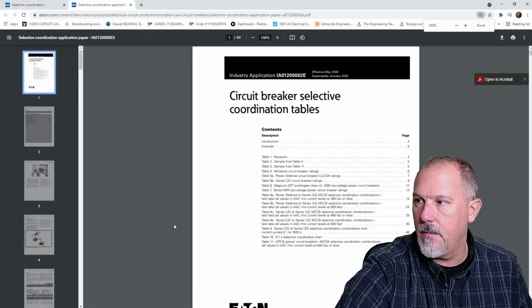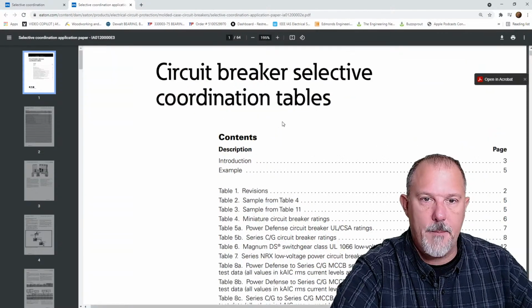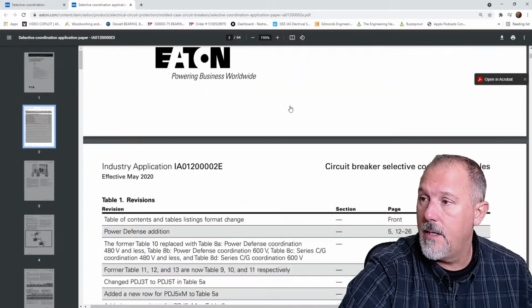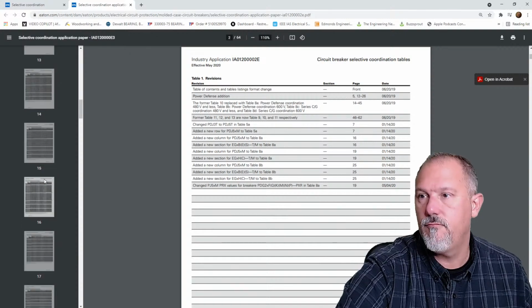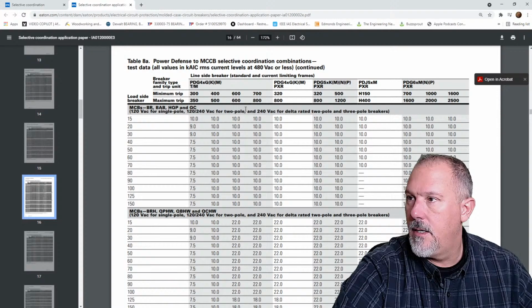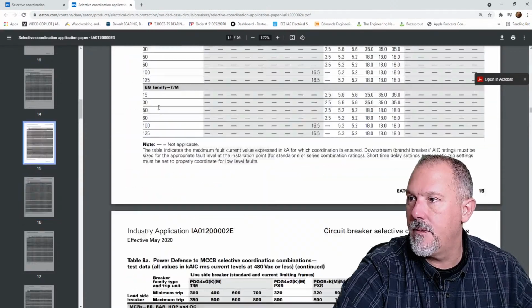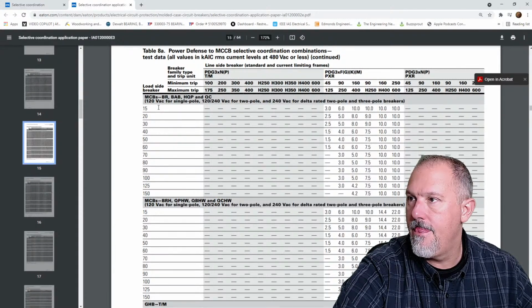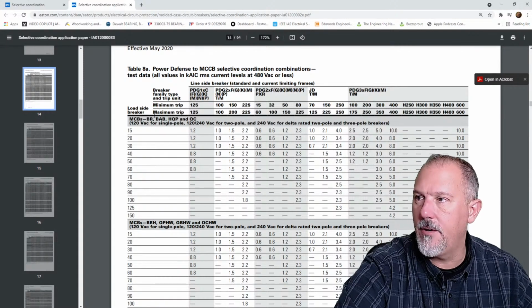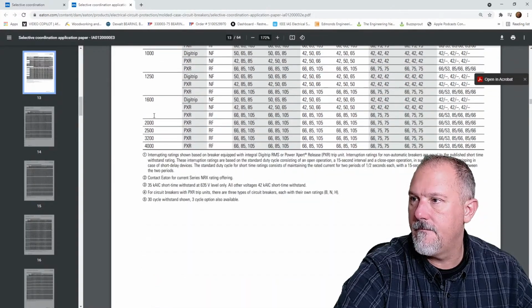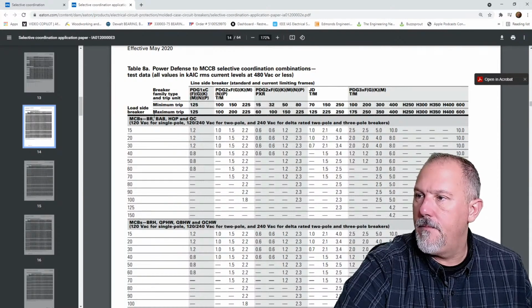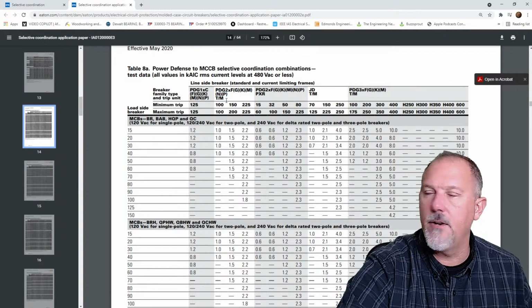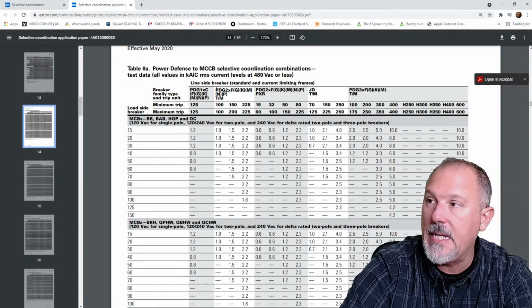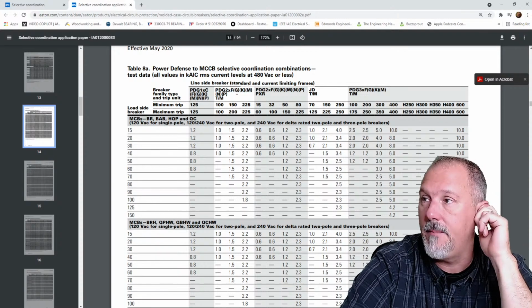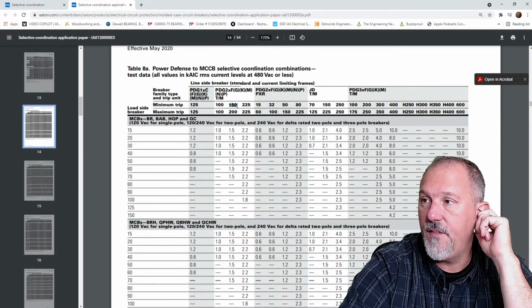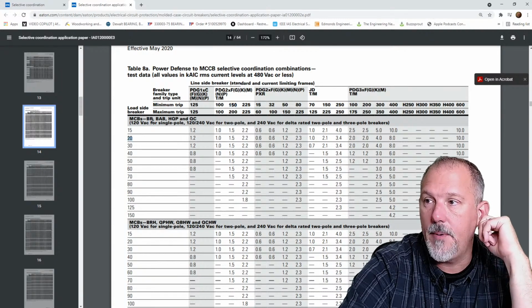Let's take a look at this application paper. Look what this says: Selective Coordination Application Tables. So I am going to find the page. Here we go. I said I had a BAB, so here's my BAB. I'm looking for the right breaker pair. All of these are Power Defense. This is a thermal mag breaker. So that FD 150 is this PDG2, which is the F frame, see the F right there, and a G frame. 150. So there's my 150 amp frame breaker. There's my 20 amp BAB circuit breaker.